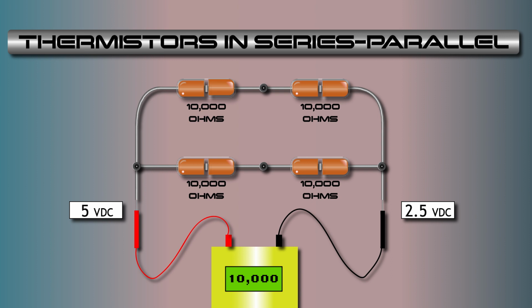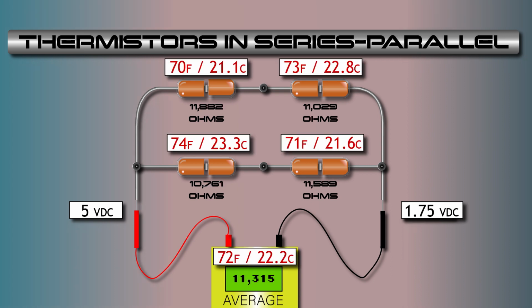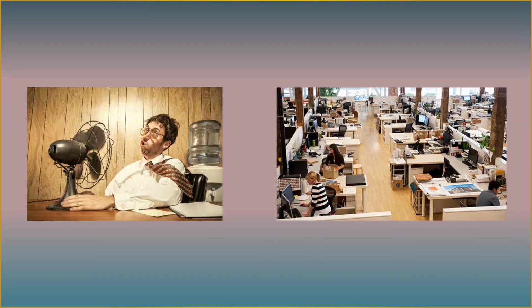But what happens is the 4 independent thermistor readings are different values based on the temperature of the space that the sensor is in. They all get averaged and report one temperature to the thermostat. The thermostat has no idea that actually 4 sensors are hooked up instead of just one. Implementing this on a problem job site could help the unit more evenly control the space.